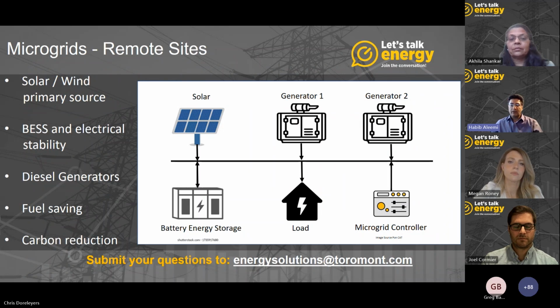Generators will recharge the battery and also provide power to the load. Once the batteries are fully charged, generators will go offline and the cycle repeats. Solar will be energizing the load with the backup of batteries. In this application, we can see that with having a battery bank system, we don't need to run the diesel generators as often, and the customer could save fuel and reduce carbon production. If we can go to the next slide, please.